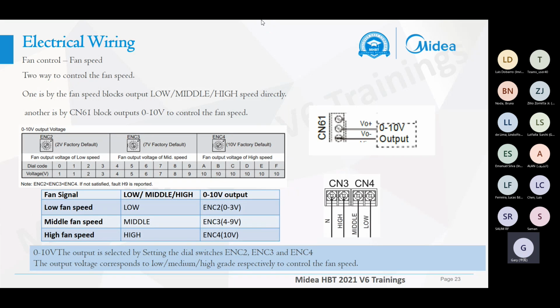And for the fan controls, we have two ways to control the fan speeds. We can directly connect to the CN3 and the CN4 to achieve the three fan speeds. So three fan speeds: the high, the middle, the low. We can also use the CN61 to control the fan speed via the 0 to 10 volt output. But for the CN61, use this.